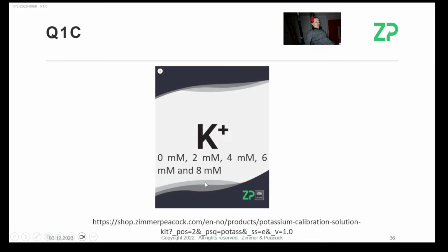Just on the calibration solution, the solutions they bought, they have 0 millimolar, 2 millimolar, 4 millimolar, 6 millimolar, 8 millimolar. If you come on our course, our workshop, I will laugh about the 0 millimolar. The reason is there's an equation behind how an OCV, or open circuit voltage, or open circuit potential, or ion selective electrode sensor works. There's an equation behind it, which is the Nernst equation, which says the signal is proportional to the log of the concentration. The log of 0 is infinity, so it sort of breaks the equation that we have behind it, but it does work.